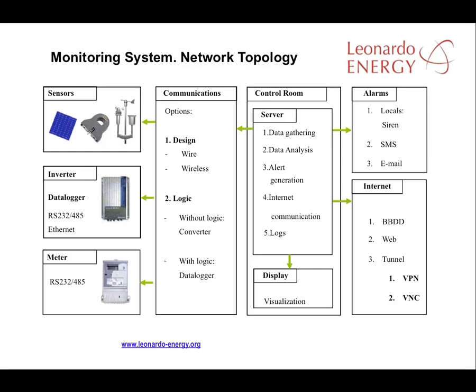There is also a choice between logical and non-logical communications. With non-logical communications, we have to use a converter. There are many of them on the market. The most common one from Moxa converts a serial bus to a different type of bus. Alternatively, we can use logic in our communications using a data logger that gathers data from all the devices and allows that data to be easily analyzed by a different computer.